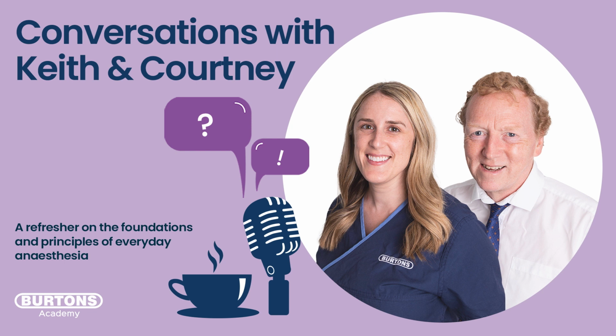Underdamping is a different thing, and actually underdamping is where you haven't got enough spring in the walls. There has to be a degree of spring. Otherwise, we get into this situation we call resonance, which, again, is another physics term. But basically, if you imagine the upstroke of the IBP waveform, it is an upstroke, and then it's a little peak and then back down again. If you've got underdamping, that shoots up too far. And then as it comes down, it shoots down too far, and you get what we call ringing. And you can see little extra spikes appearing at the turning points of the waveform.